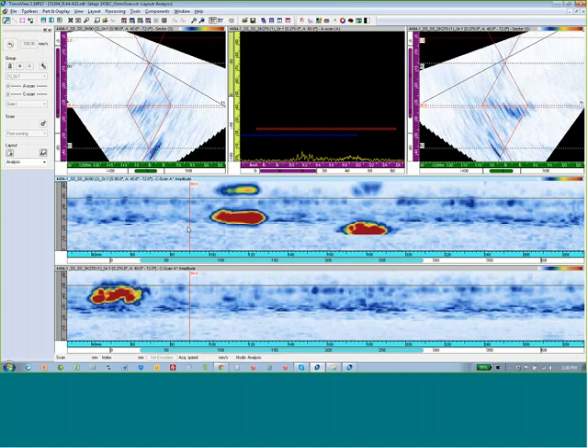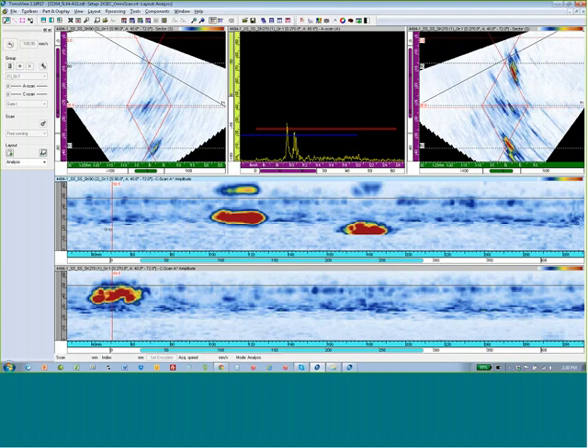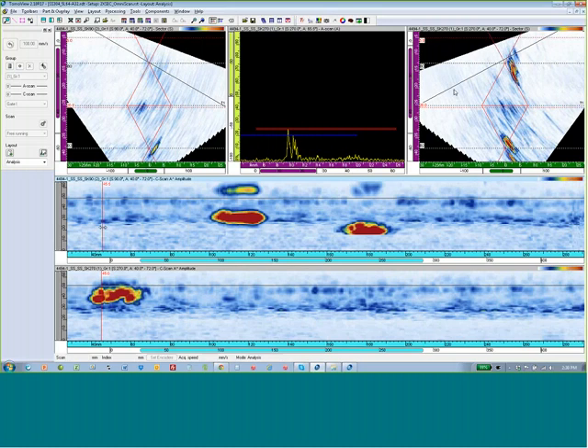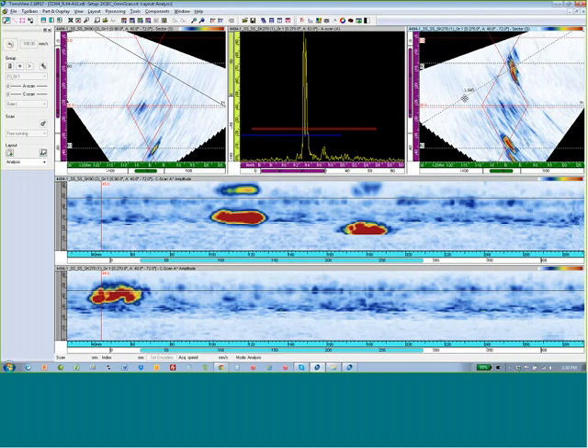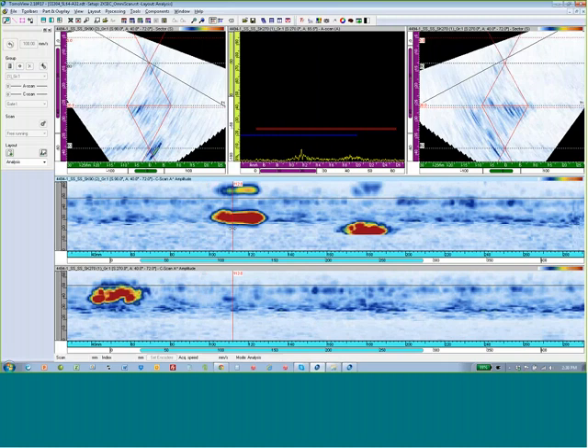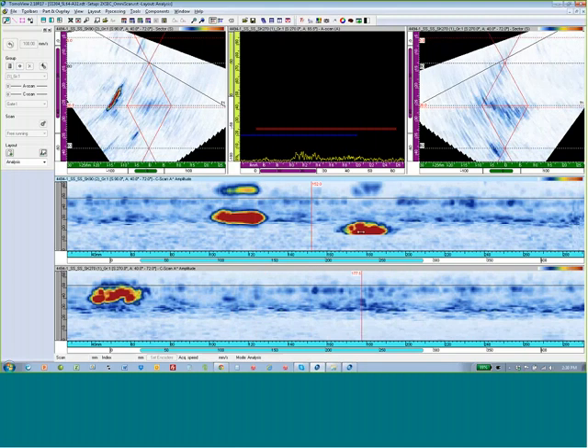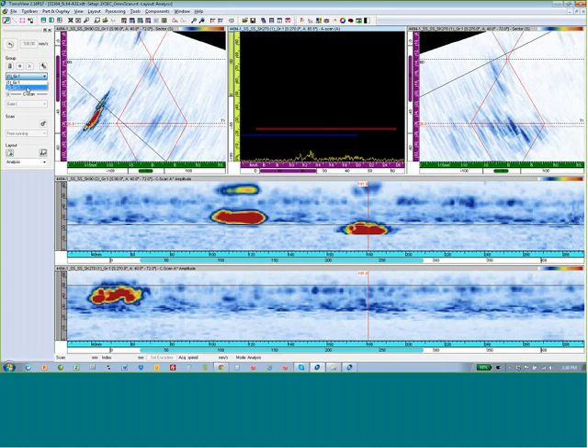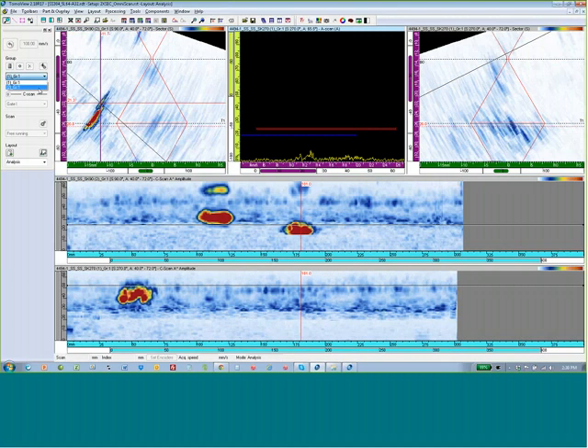In this case, it's an austenitic weld, and we can still see very good A-scan crack characterization. We would expect precision sizing similar to a standard S-scan with added benefit of closer inspection to the weld and greatly improved coverage. In this case, here is our small crack tip. We'll zoom in on this, update the A-scan. We'll put one cursor right on the tip of the crack and another cursor at B0, representing the through-wall dimension for the overall through-wall dimension of the crack.